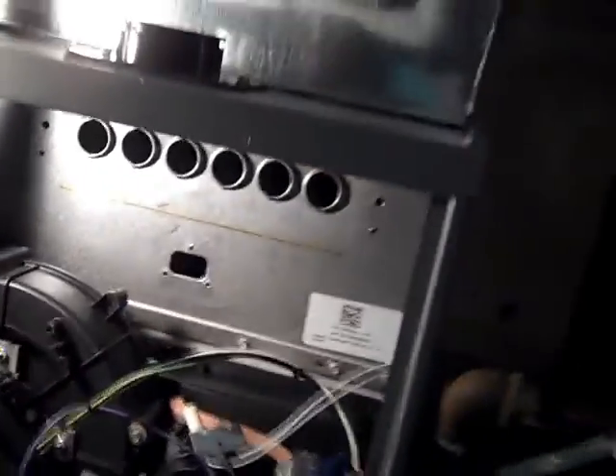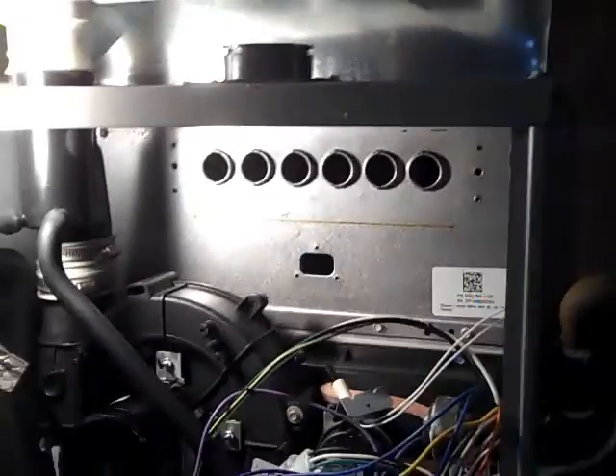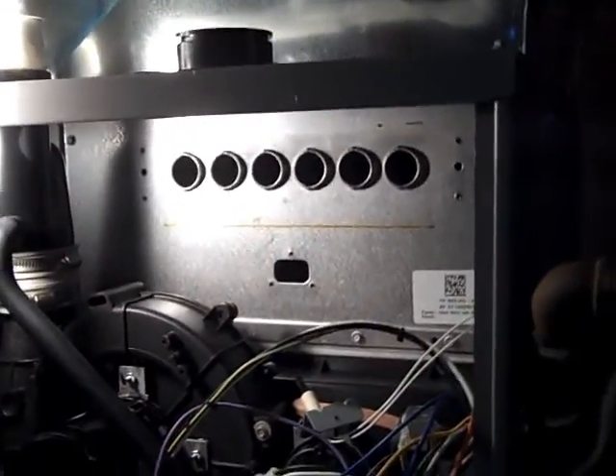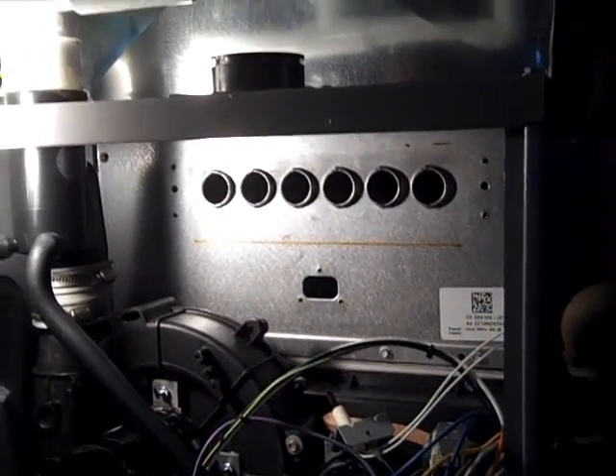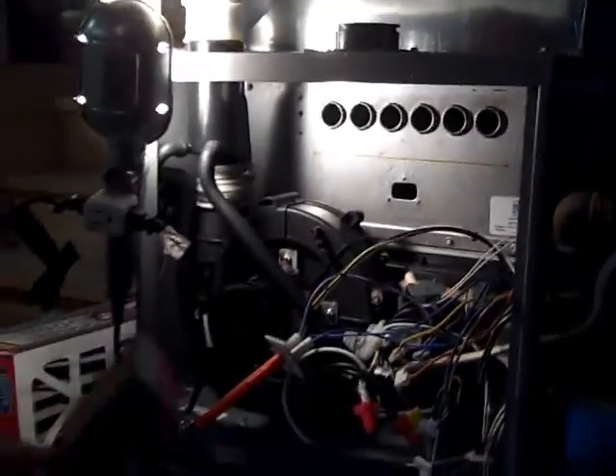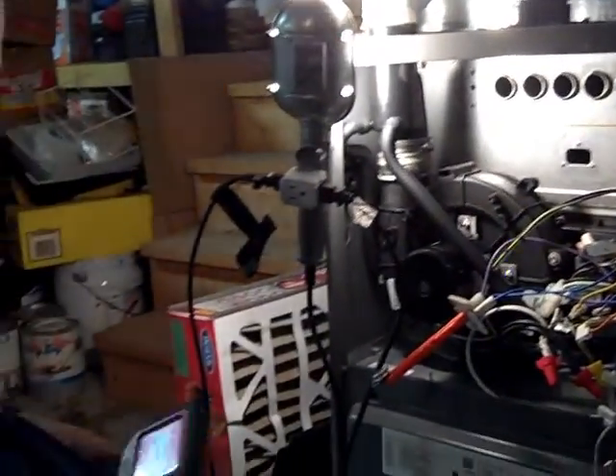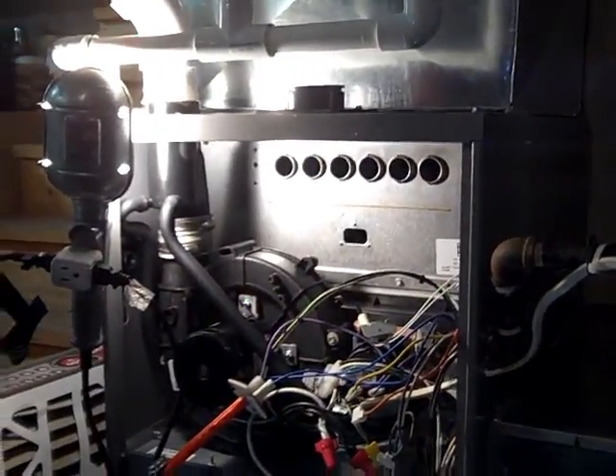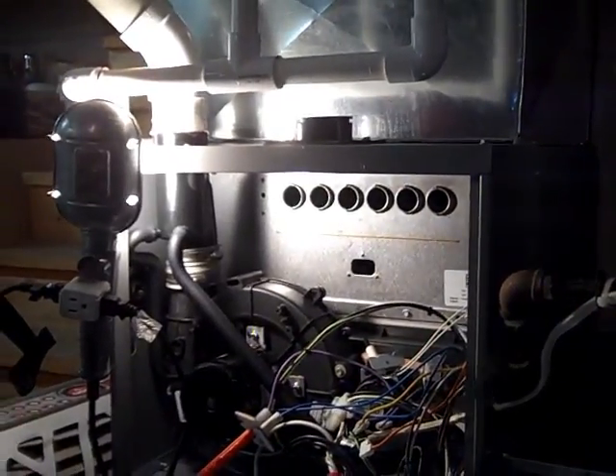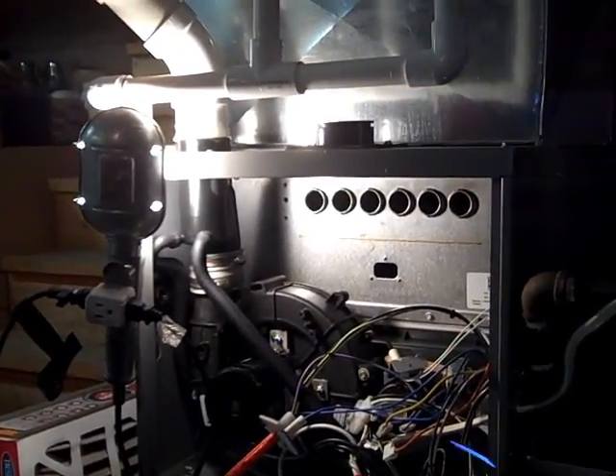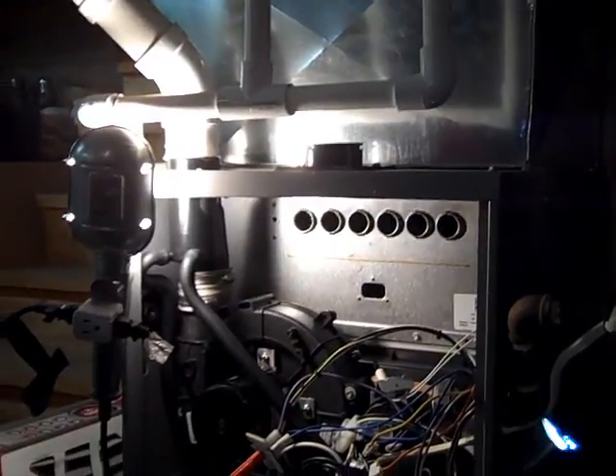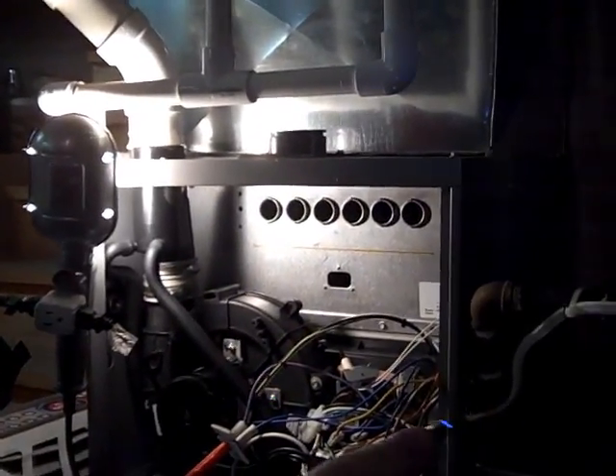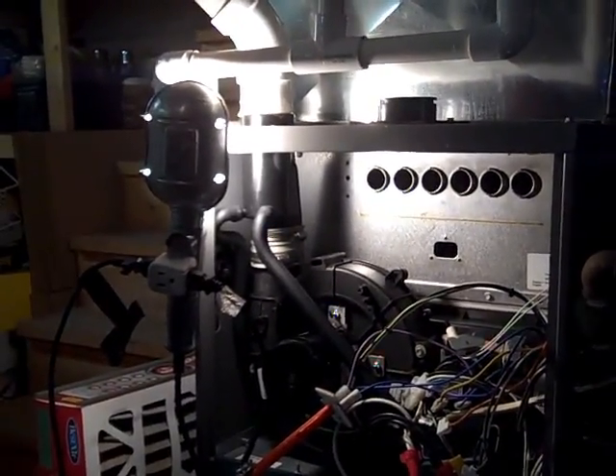Alright, well, as we see here, the burners are still out, and now the thermal cutout, the main limit, is out, and Kevin is connecting up his borescope, and he's going to take a look inside at the heat exchanger. Now, this is a relatively new furnace, not very old, but this is one of the parts we still have to look at. It doesn't matter what the age is, you still got to look back in there.